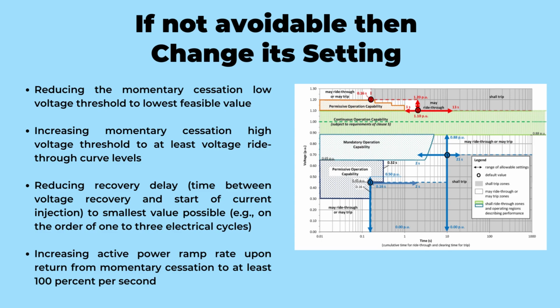Fourth one is increasing the active power ramp rate upon returning from momentary cessation. Boosting the active power ramp rate to at least 100% per second enables the inverter to rapidly ramp up its power output once momentary cessation is resolved, contributing to a more seamless power flow. These measures hold the potential to optimize the performance of legacy inverters, even in the presence of momentary cessation. By implementing these strategies, we can enhance the stability and reliability of power systems.